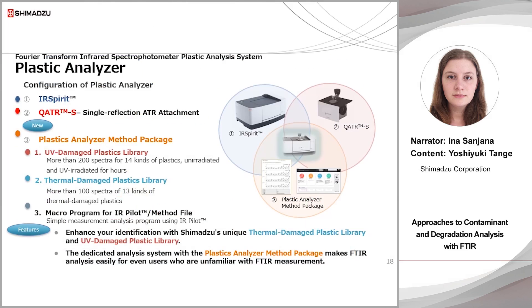Shimadzu has released the plastic analysis system Plastic Analyzer to assist in plastic analysis, including degraded plastics. The Plastic Analyzer consists of the Fourier Transform Infrared Spectrophotometer IR Spirit, QATR-S as an attachment for single-reflection ATR, and a method package. The UV Damage Plastic Library and the Thermal Damage Plastic Library allow accurate analysis of degraded products, and the method package supports IR pilot measurements. This enables a simple FTIR workflow which can be carried out even by inexperienced users.